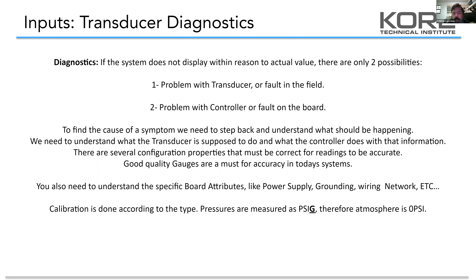To diagnose a transducer, you need to understand what the controller is doing and know the different configuration properties. Good, accurate gauges are important, especially for calibration. You also have to understand the circuit board's baseline — the board's power supply and grounding network — just like any input. But if you've got one reading that's off and the rest of everything on that board is reading right, you probably wouldn't need to waste your time checking the board's power supply.